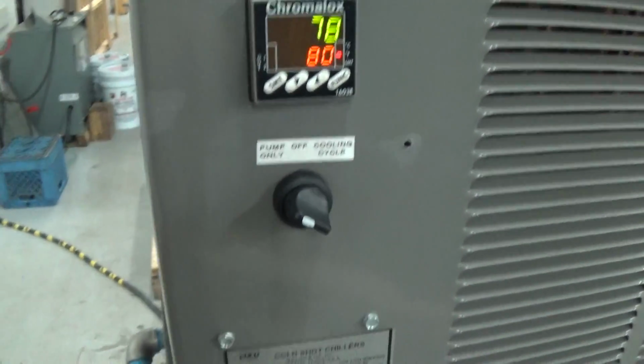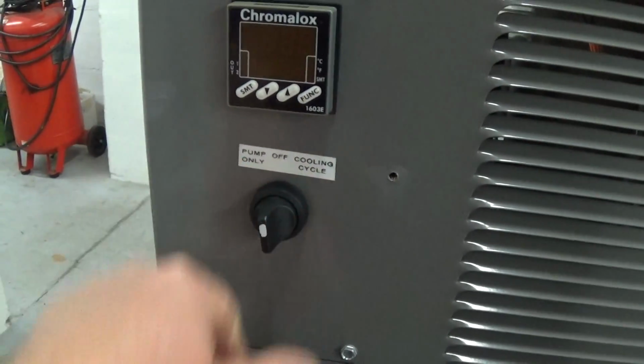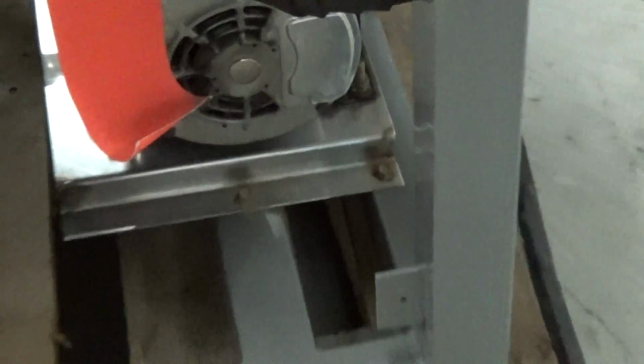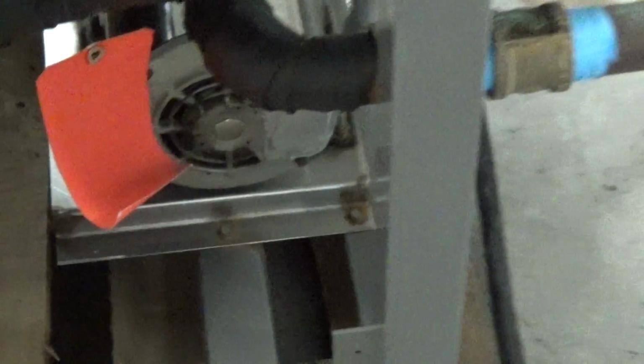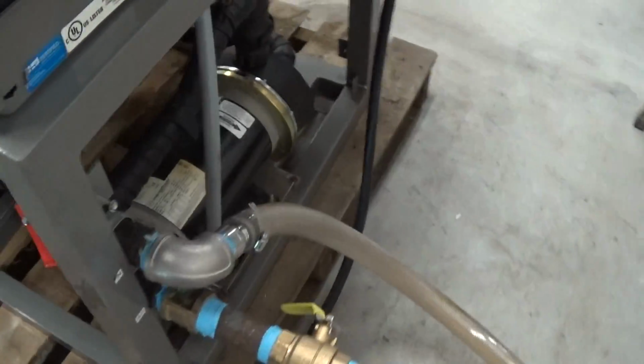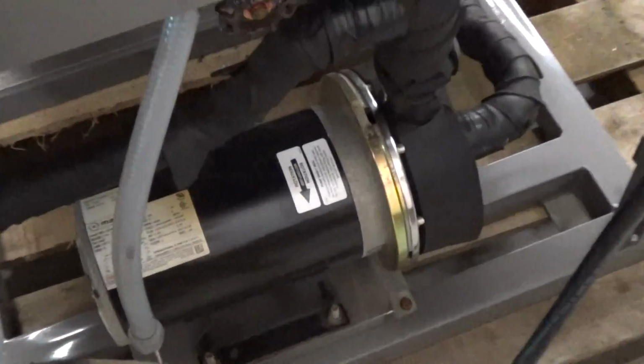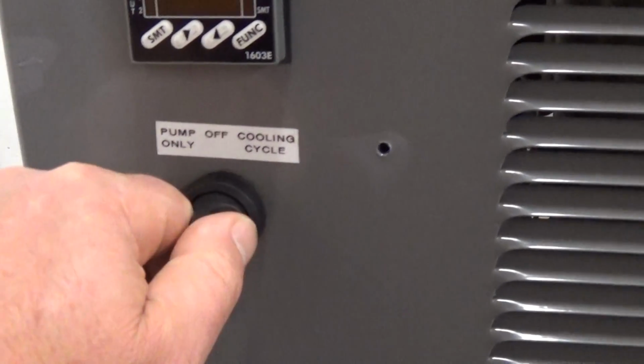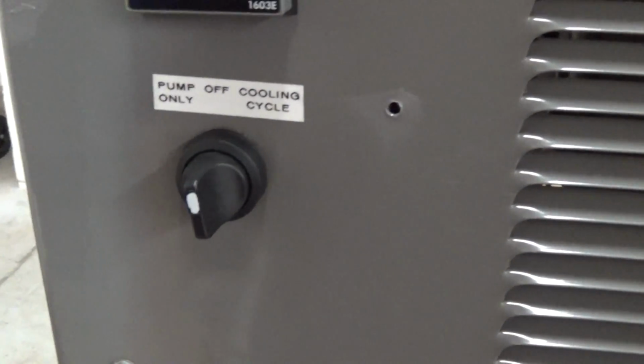And when you first start it up, you'll want to have somebody looking at the back of the pump here and make sure you have the pump rotation correct. This is a 3-phase pump and a phase-dependent unit. When looking at the back of the pump, you want to see that it's going clockwise from the rear of the pump, just like you see there.